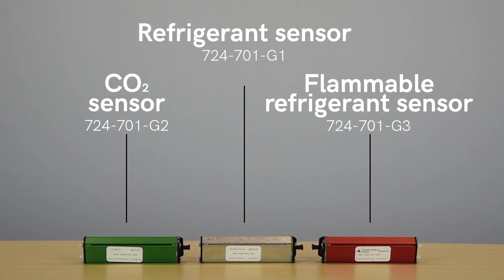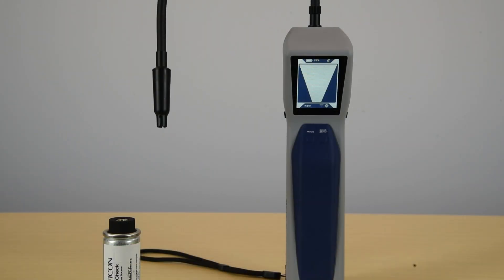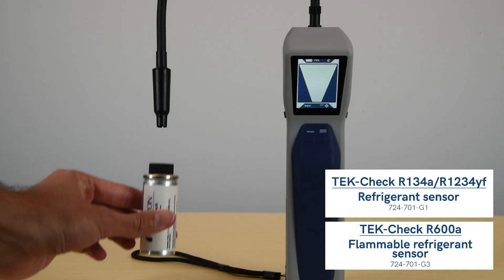To test to see if your sensor is working correctly, put Stratus in pinpoint mode and check it against a TEK-Check or a refrigerant reclaim tank. If the leak is detected, refer to our video on the various modes for the Stratus.